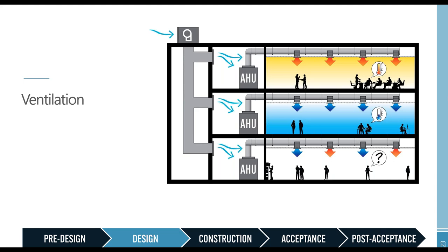And we finally got back to the table and got our way. The system airflow was balanced to the appropriate outside airflow rates to match what the air handling units could handle. And we're currently still working with the building now, and this issue appears to be closed.